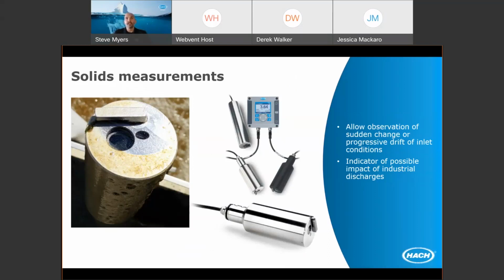So what you see here is some windows. This sensor uses an infrared duo scattered light method, allowing a highly accurate suspended solids measurement that's independent of color - no influence from the color of the water. We also have the all-important self-cleaning wiper to keep that window clean from biological growth, and it's worth considering different wiper materials for different types of pollutants.